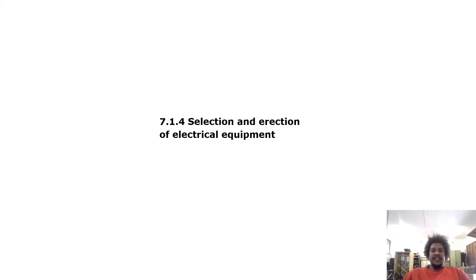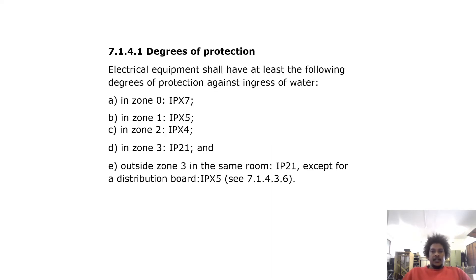Selection and installation of electrical equipment — degrees of protection: electrical equipment shall have at least the following degrees of protection against ingress of water: in zone 0, IPX7; in zone 1, IPX5; in zone 2, IPX4; in zone 3, IP21; and outside zone 3 in the same room, IP21 — except for distribution boards, which require IPX5.